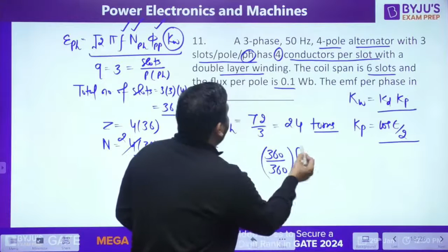Per slot electrical angle: total 360 is the mechanical angle and total slots are 36, so this is the mechanical angle per slot. Multiply it with P by 2 to get the electrical angle per slot, which we call the angular slot pitch. So the angular slot pitch came out to be 20 degrees. For per slot, electrical angle is 20 degrees.